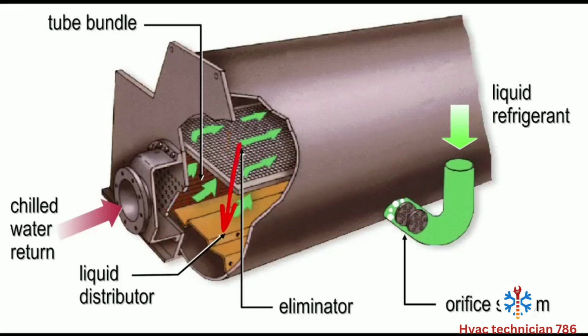Either way, we enter the bottom of the evaporator. This is a flooded evaporator. Our refrigerant is on the outside. This is a shell and tube heat exchanger, and our water is inside of the tubes. We come into this distributor at the bottom of the evaporator. This is this rail that sits underneath the tubes. This will make sure that all the liquid refrigerant coming in gets distributed across the full length of the evaporator. It will then flow up and hit the tubes as a saturated refrigerant, and we want to make sure that we're pulling across the entire length of the evaporator.